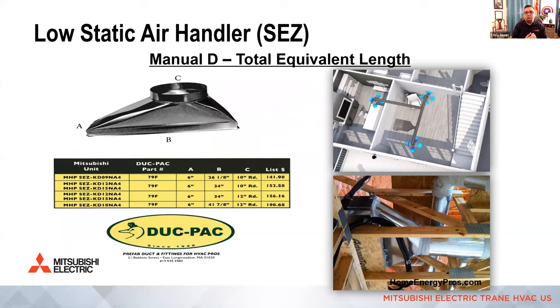If you're going to run a round trunk, as an example here, a lot of our distributors for Mitsubishi work with Duc-Pac out of Massachusetts. And you can see they make a standard 10 or 12 inch starting collar for these SEZ air handlers to go to round trunk. So that way it's a long throat and they have a really low value. If you were just to put a box and you were still going to try to run a trunk off of that and take anything off the side, those fitting values become very high when you do this.